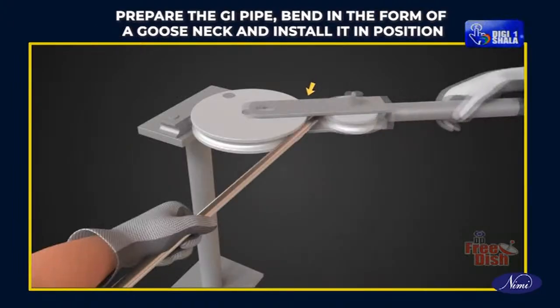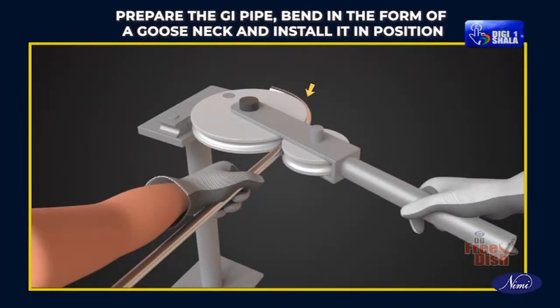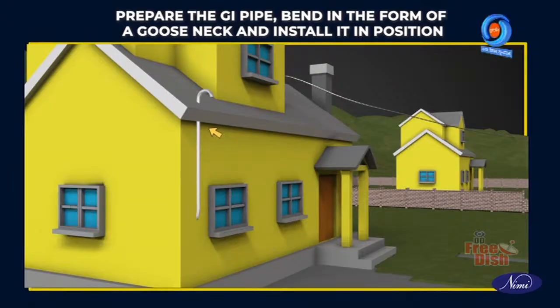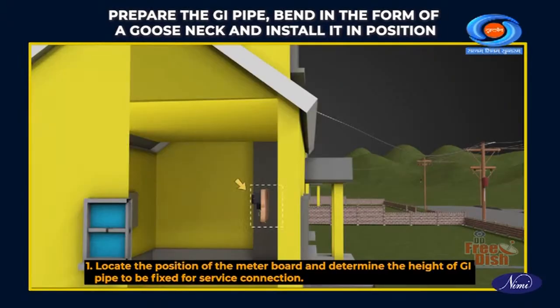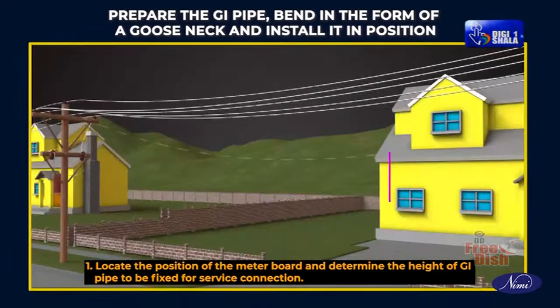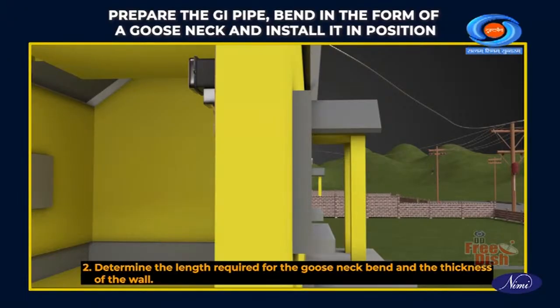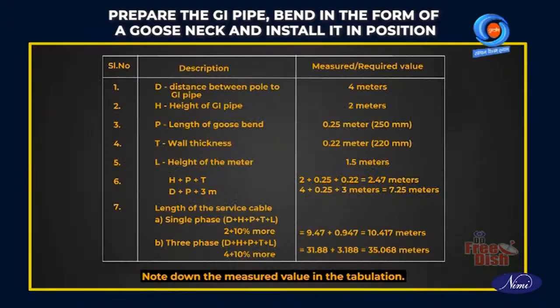Prepare the GI pipe, bend in the form of a gooseneck and install it in position. Now, locate the position of the meter board and determine the height of GI pipe to be fixed for service connection. Determine the length required for the gooseneck bend and the thickness of the wall. Note down the measured value in the tabulation.